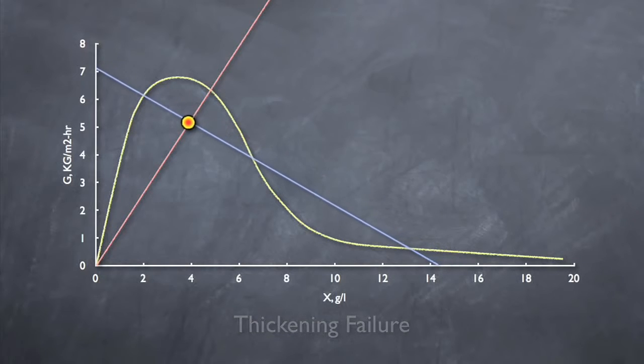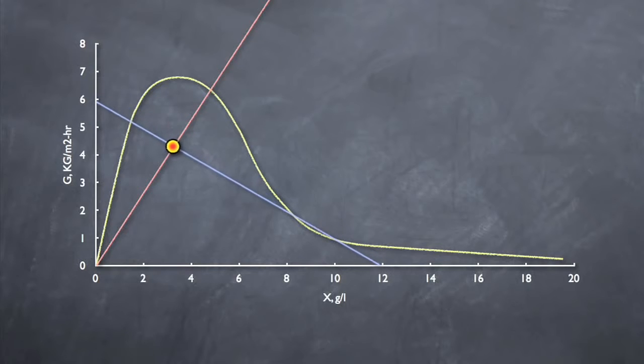So if either of these scenarios should occur, and you were to fail in thickening or clarification, there is some good news. The system will eventually fix itself. How? Well, if solids are passing over the weir, the concentration of the system will decrease. And as we've already covered, a lower mixed liquor concentration will move the underflow line back towards the origin and eventually under the settling curve.